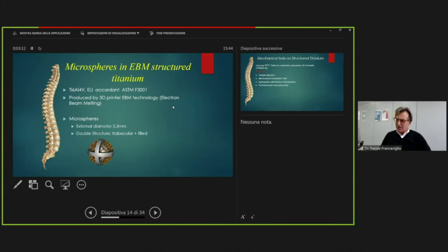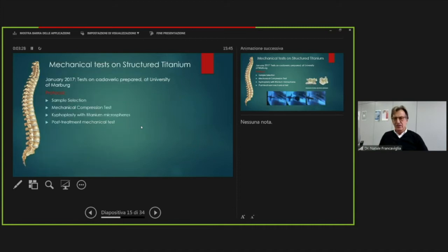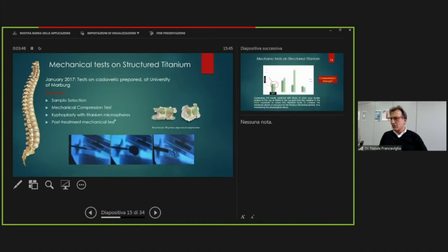It is an EBM technique, and the technology is the sintering of titanium. You can see here the characteristics: 3 millimeters wide with a double structure, trabecular and filled structure. In 2017 we made the first biomechanical test at the University of Marburg. You can see here the mechanical compression test, the kyphoplasty with the microtitanium and the post-treatment mechanical test.